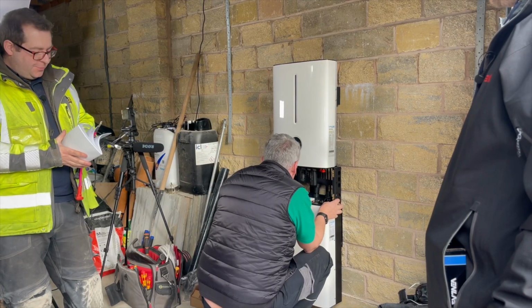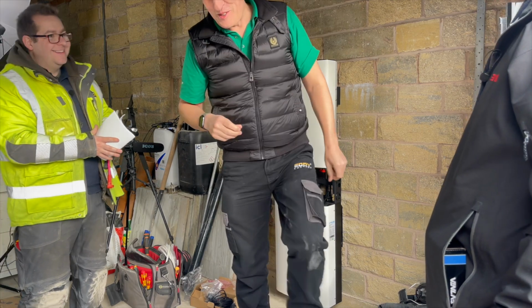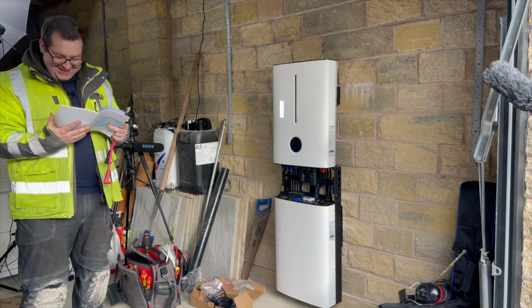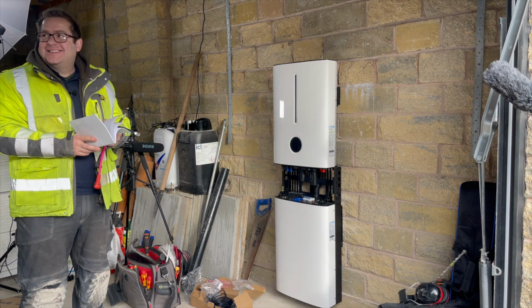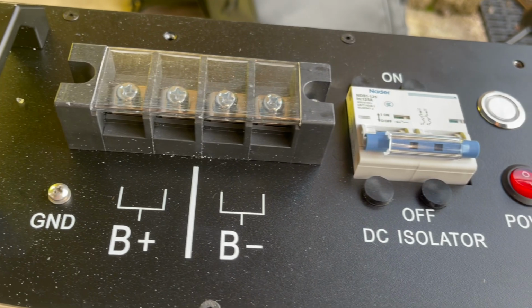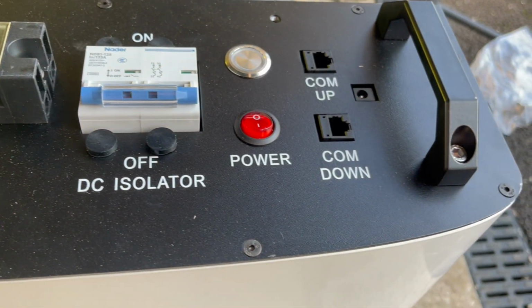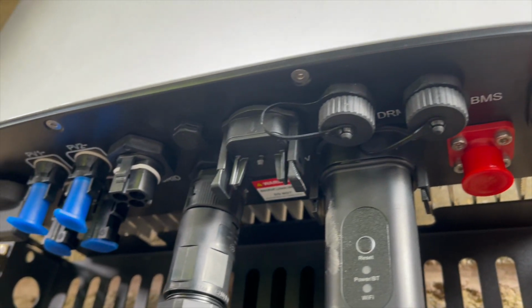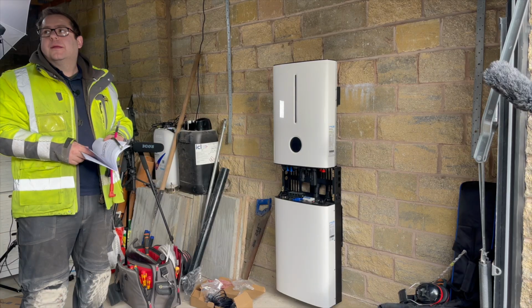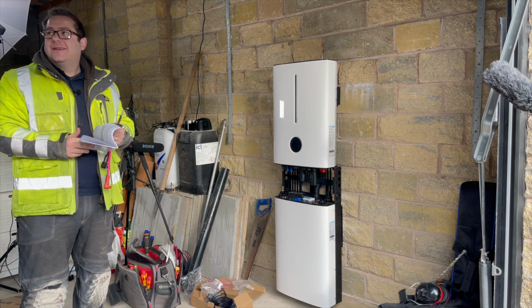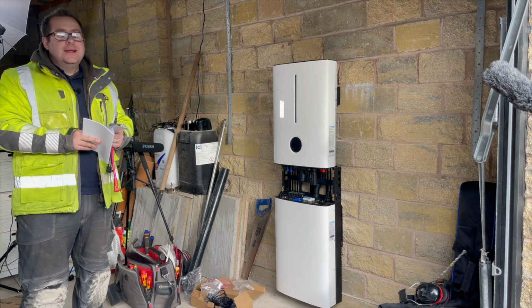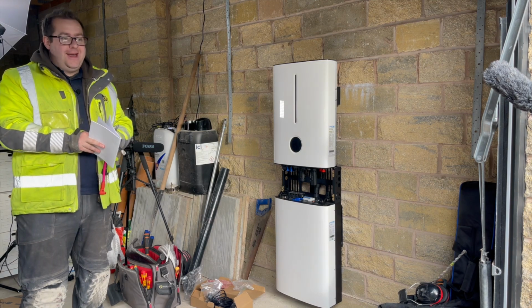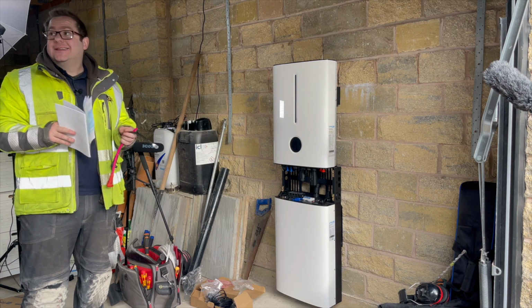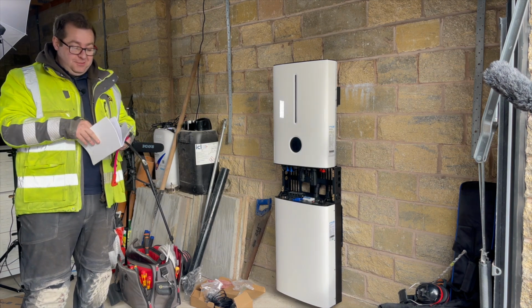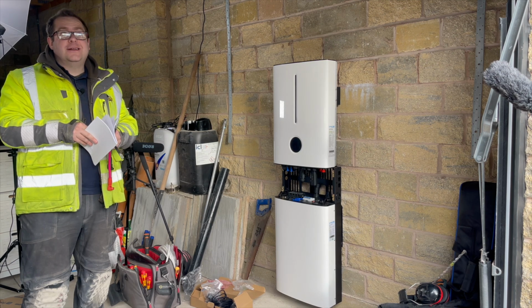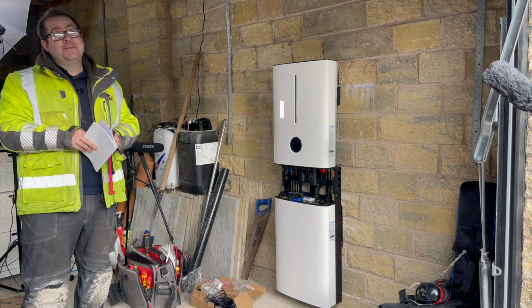That's another thing as well. Do you prescribe to this? Do you fit isolators or not? Yeah, so I'm going to. I always put in my head, what would I do if I actually had a proper job? If you want to isolate the strings, you've got an isolator on there, which if it's got the right IEC numbers compliant, you would knock that off and physically disconnect the plugs if you wanted isolation. So, and fit. Now, I know literally all the software, when you spec a system, if it's got a DC isolator, it doesn't spec a system. And I was told on the training, you've got to have one still. Now, I hadn't got one, and I still passed the MCS accreditation.